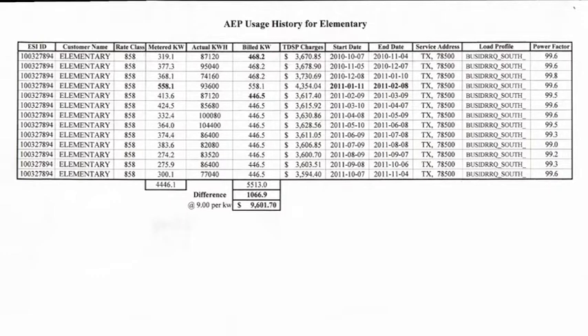The difference is 1,066 kW between the billed and the metered. And so the hit for that one day is almost $10,000 a year that you didn't have to pay. All right? But you're not watching, and everybody wants to be warm. Everybody's warm, everybody's happy. What he was alluding to, and I see, is the more efficient you make your air conditioners, the worse your electric heat becomes, because now you've got a bigger disparity with what you're actually doing and saving.